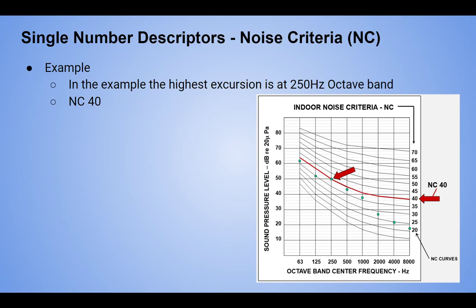The problem is: given that this room is NC 40, we don't know we need to control at 250 Hz — we don't know we need to address something there. It could be that 250 Hz isn't the issue; maybe it's down at 4k, around 38–40 dB. That's the misleading part of an NC value. But it's used everywhere, so it's helpful when starting — you just need to know its limitations.